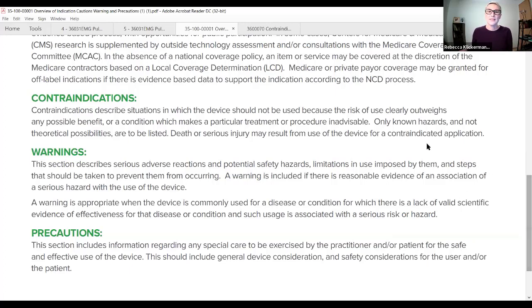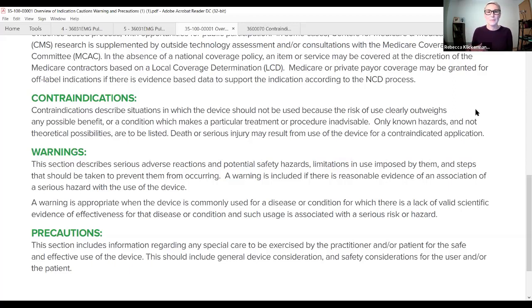A warning describes a serious adverse reaction, potential safety hazards, limitations in use imposed by them, and steps that should be taken to prevent them. A warning is included if there's reasonable evidence of an association of a serious hazard with the device, or when the device is used for a condition lacking valid scientific evidence of effectiveness and such usage is associated with serious risk. Precautions include information regarding special care that the clinician and/or patient should exercise to ensure safe and effective use of the device, covering general device and safety considerations.